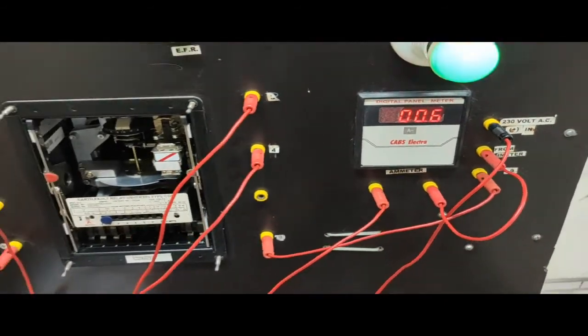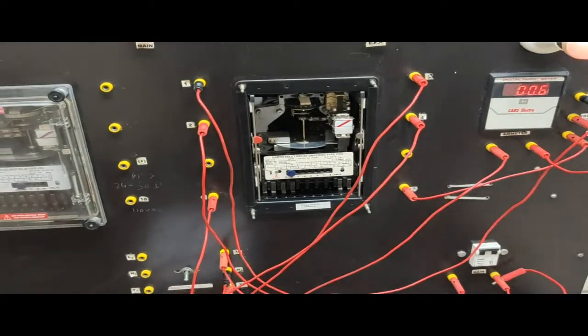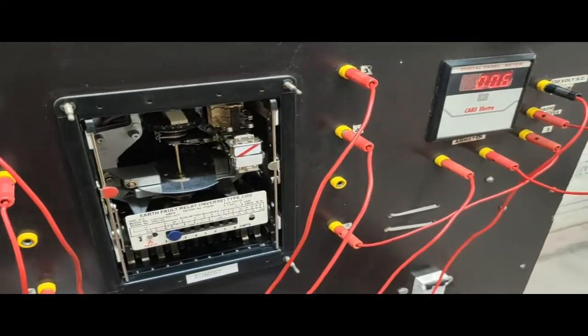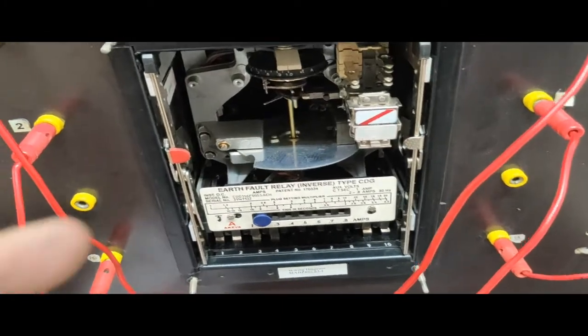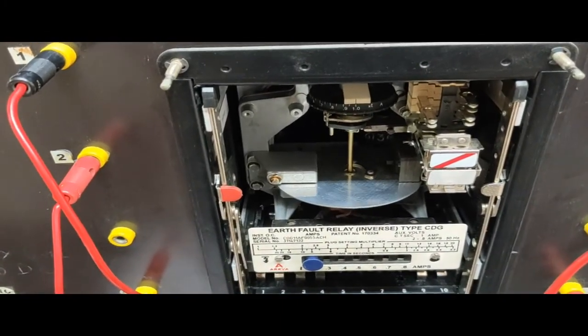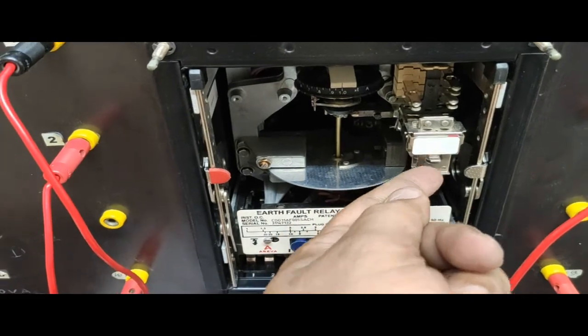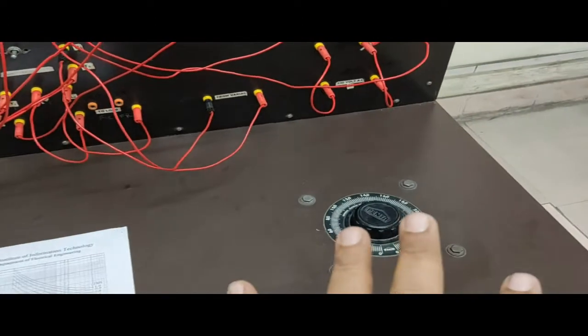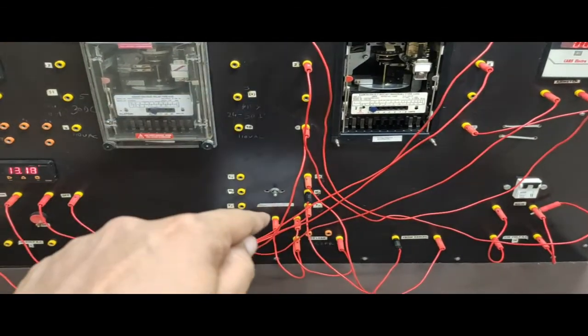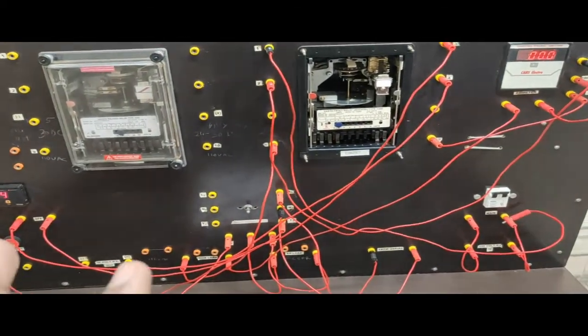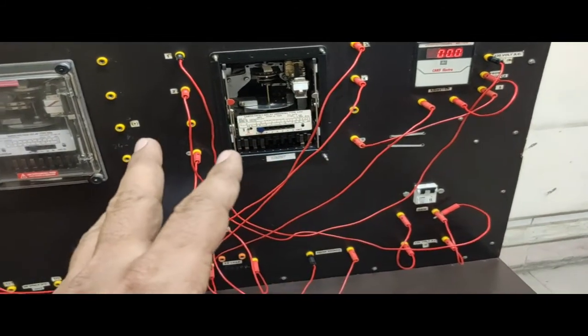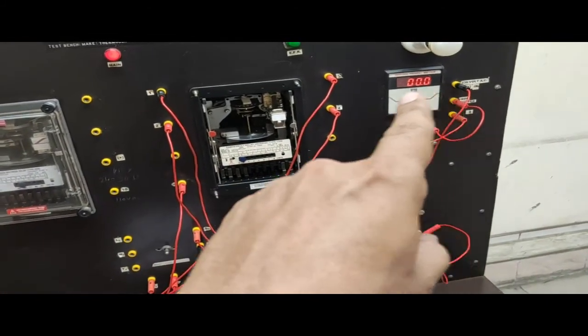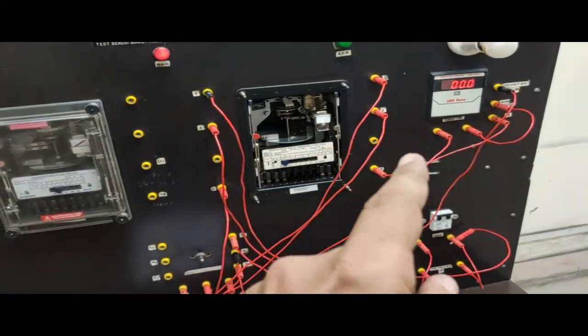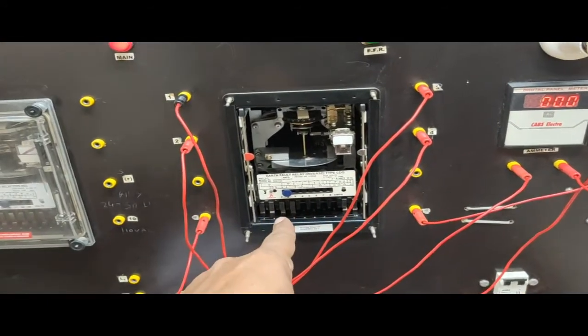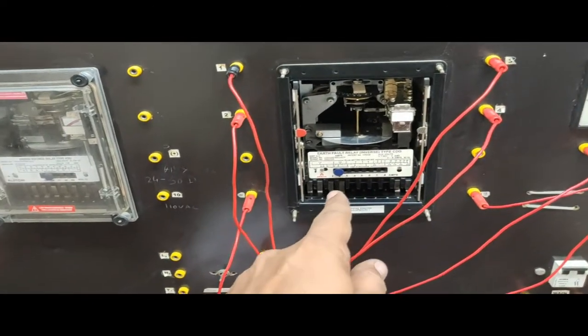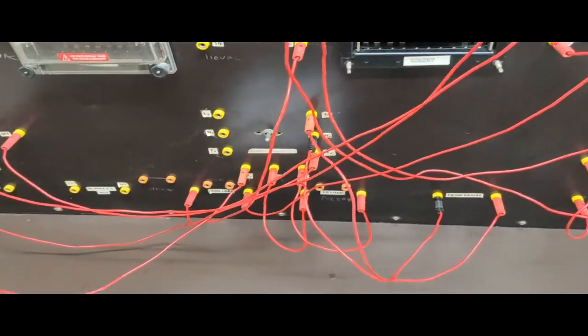So now I am creating the fault using the variac, so that if I now make everything normal, I disconnect the circuit. As I disconnect the circuit, due to the spring action, the relay comes back to the normal position or the initial position. So just pull the plug up. Now I do not touch the variac. So if I again move the selector switch in the downward position, then what happens? Then the required amount of voltage will be applied to the relay and 0.6 ampere current will flow through that particular relay coil. And as the relay coil current is 0.6 ampere and the plug setting is 0.2, so 0.6 by 0.2 gives the plug setting multiplier as 3.